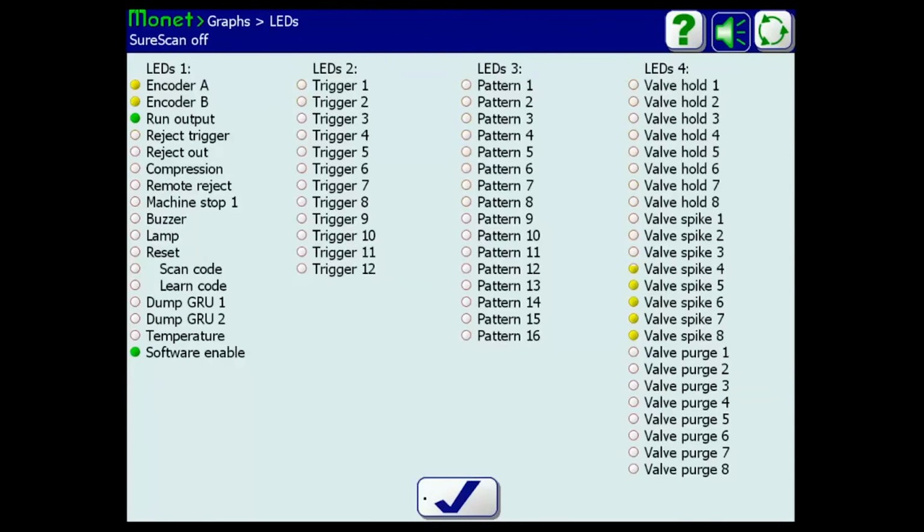Sorry. Yep. When we normally activate a glue valve, we actually use two voltage signals. We use what we call a high time spike voltage, and that's usually a very, very short duration to get the valve to open as soon as possible. And as soon as that valve is open, we no longer require that higher voltage, so we drop down to what's called a hold voltage.